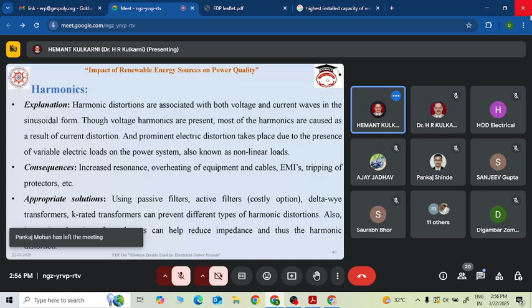What are the consequences of that? The consequences are increased resonance - I have the diagram - and cable overload. So again heating, and again the problem of insulation, because heating will definitely affect the insulation of the cable, causing relative insulation problems.